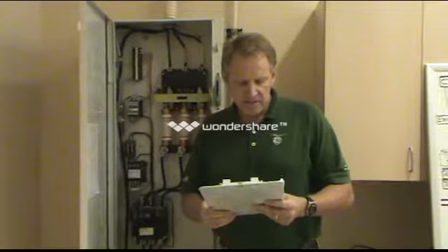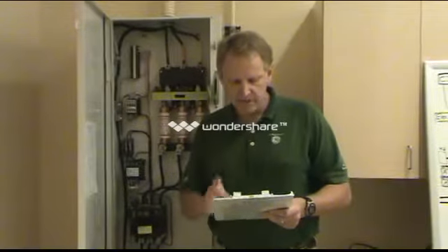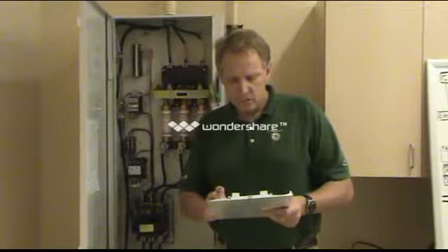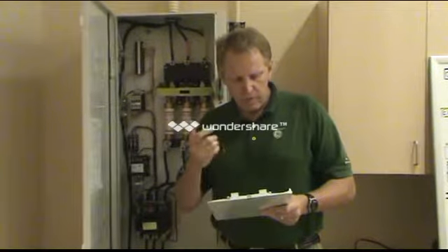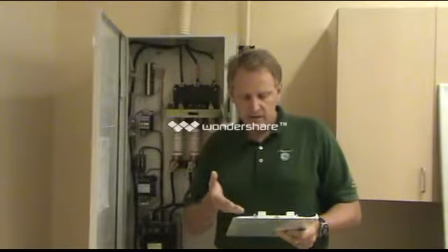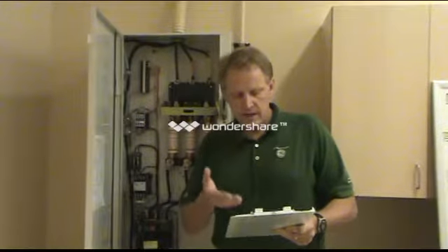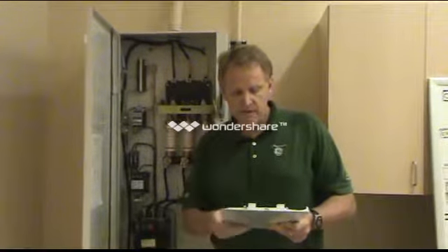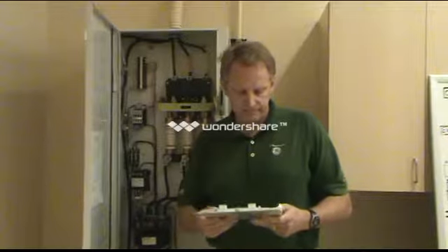All right, steps 16 and 17. They're designed for use with an impedance tester. If we can find the earth ground, we'll go ahead and do this. It's getting increasingly difficult to find a single isolated earth ground and the tools. So most often 16 and 17 will not be answered.